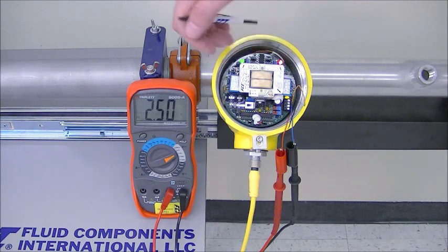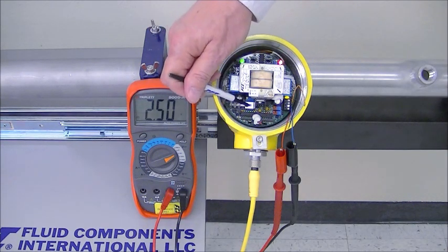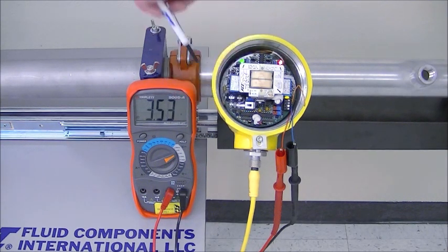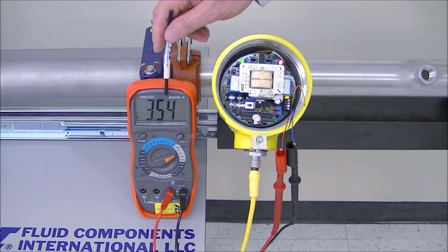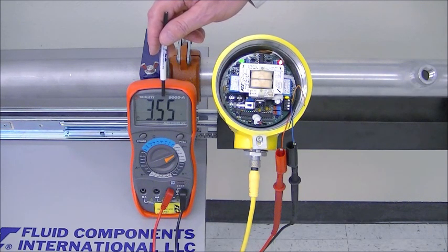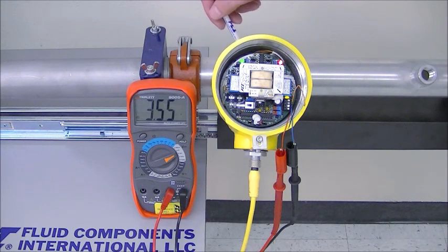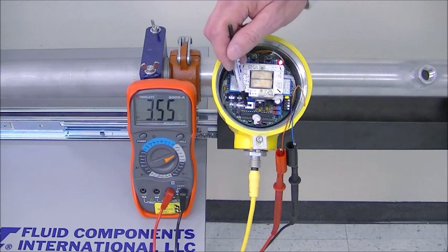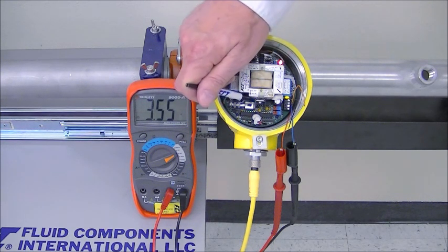So now, next thing we do is we put the switch back from the calibrate mode into the run mode. And you notice the voltage now changed to our no flow voltage again because now it's actually measuring the voltage that's coming from the sensor. When it's in the calibrate mode, it's measuring the voltage that I dial in. And when it's in the run mode, it measures the voltage that's coming from the sensor.